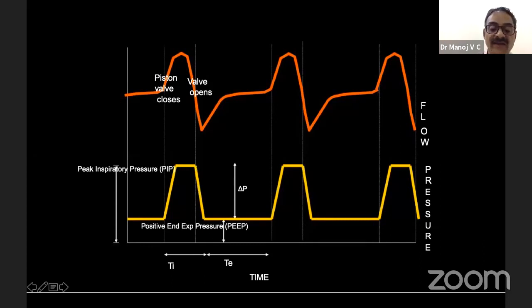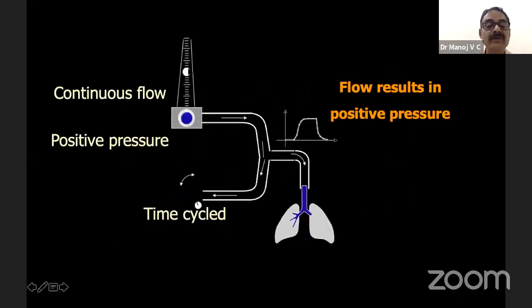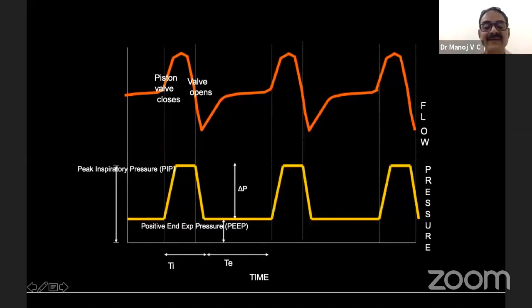Then it will fall drastically. So the time from when the valve closes until it opens is the inspiratory time. Once the valve opens, the pressure will fall until it reaches a level where the ventilator will not allow a further fall, because gas is coming from here which will develop some pressure. So it is set in such a way that it will not touch zero. This is zero. It won't touch zero. It will stop short here. This is the positive end expiratory pressure.